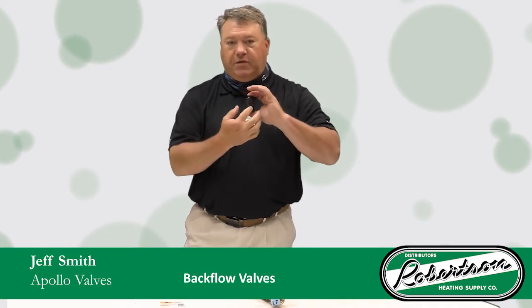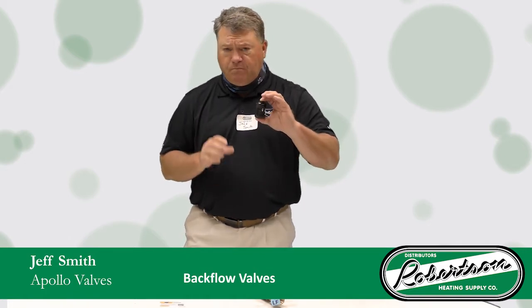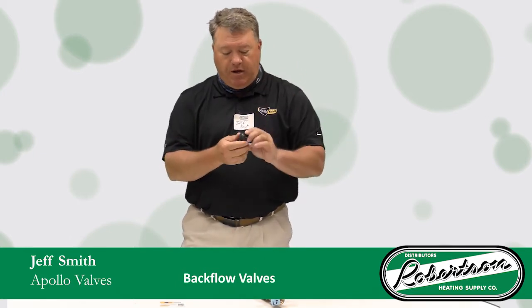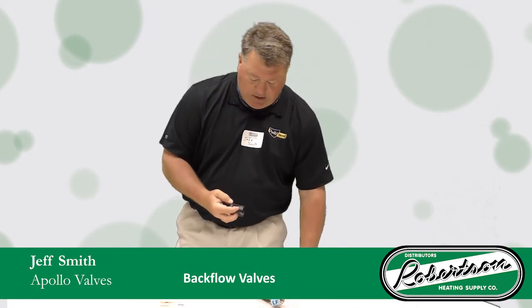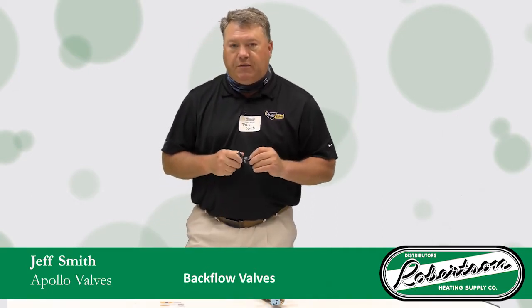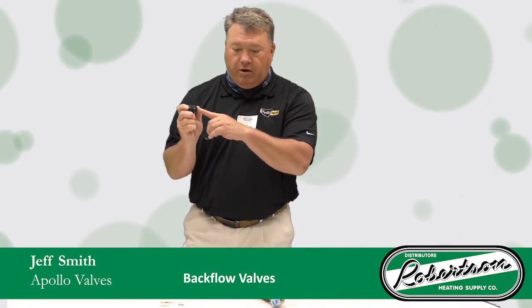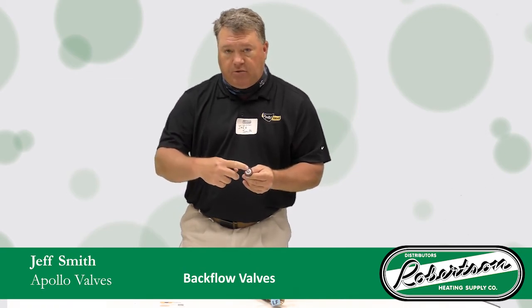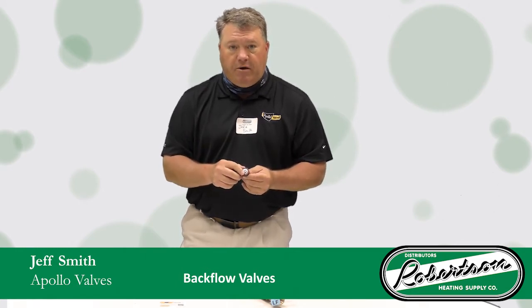On the RPZ, the difference is the spring on the first one is a little thinner than the spring on the second one. It needs a little bit more tension. In an RPZ, you also need a relief valve kit, which we'll go over in a second. But once you get this captured spring out, you can see the spring. The only items that are repairable, it's kind of like on your car. When you buy a car, your brakes are typically the wearable items that aren't under the warranty situation. On a repair kit, you have an O-ring right here. You have the red rubber right here that, in a situation where you're out at a residence or a business, you can flip over and get one extra use out of it before having to put another repair kit in place.